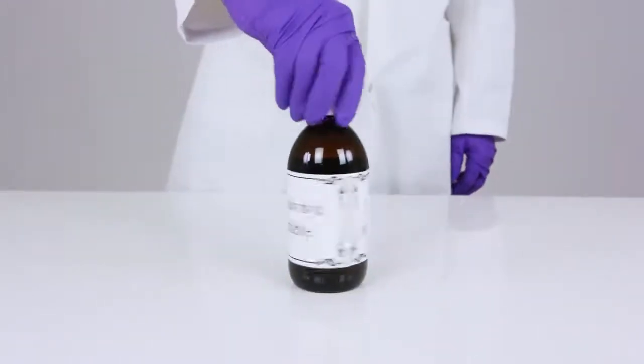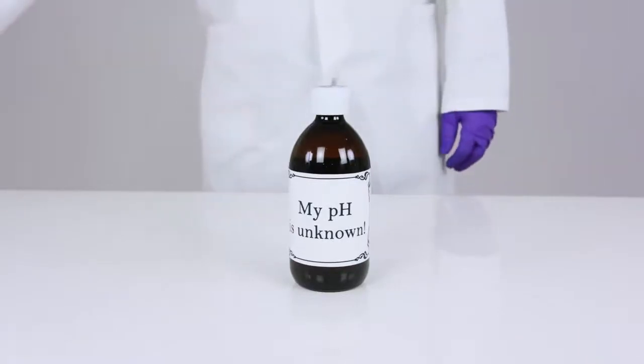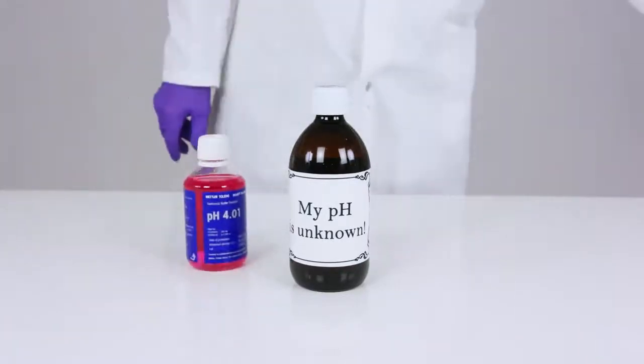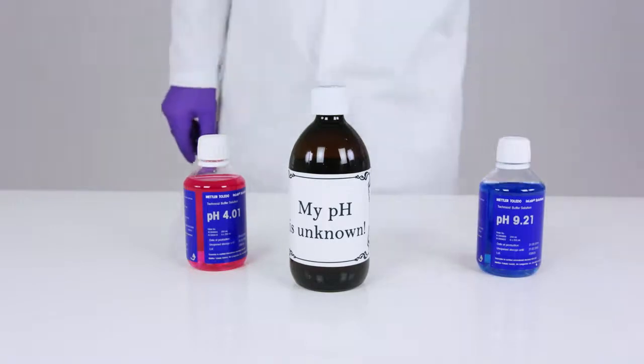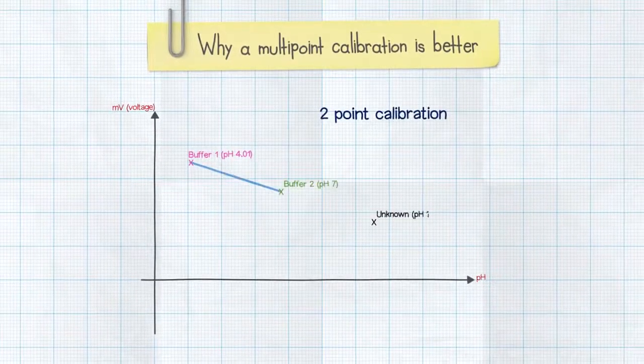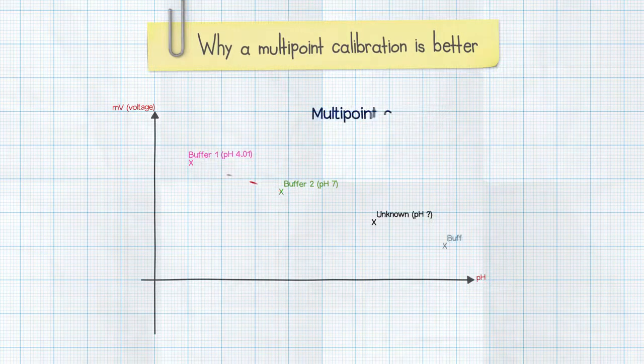If you have no idea what your sample is going to be, or if you're going to be measuring samples with varied pH values, then it's best to use a multi-point calibration to provide a wider calibration range. If you measured these varied samples with only a 2-point calibration and the pH sample happened to be out of this range, the reading would be inaccurate. We use a 3 or more point calibration to provide a wide range without affecting the accuracy of the measurement.